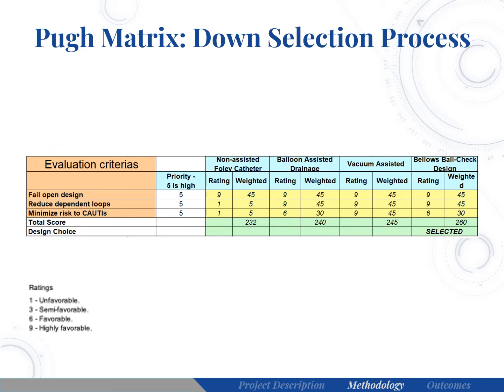First, the design needed to fail open, meaning that if the design failed, the catheter line would remain open. Second, the design must mitigate dependent loops to reduce the volume of stagnant urine in the catheter line. Lastly, we wanted to minimize CAUTI risk.